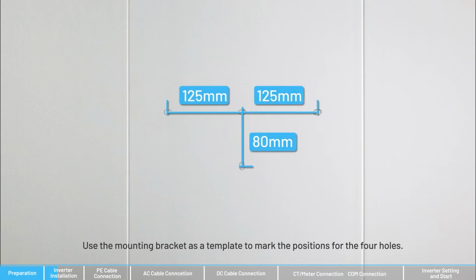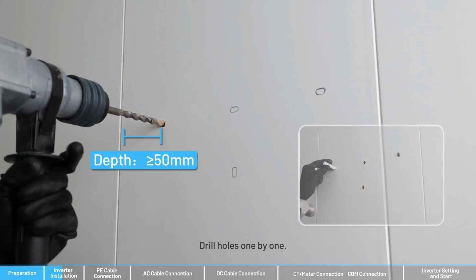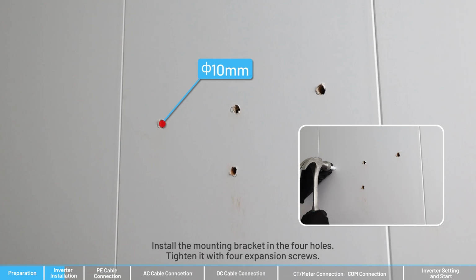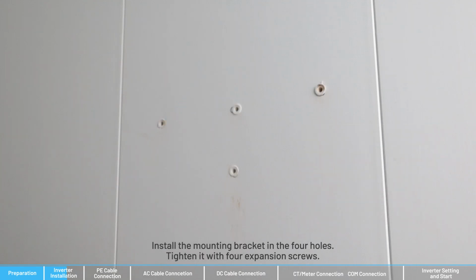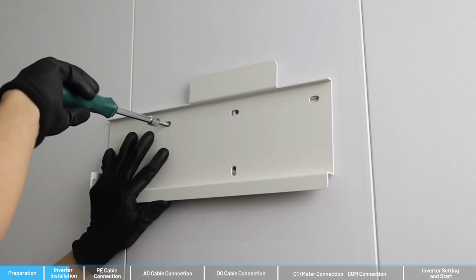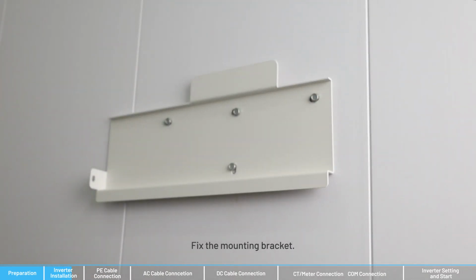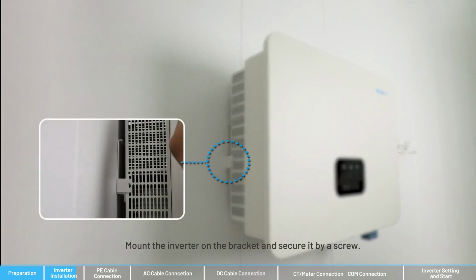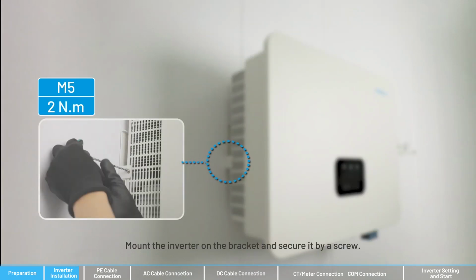Use the mounting bracket as a template to mark the positions for the 4 holes. Drill holes one by one. Install the mounting bracket in the 4 holes. Tighten it with 4 expansion screws. Fix the mounting bracket. Mount the inverter on the bracket and secure it by a screw.